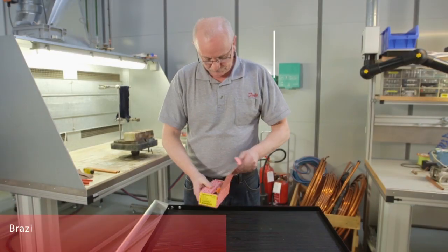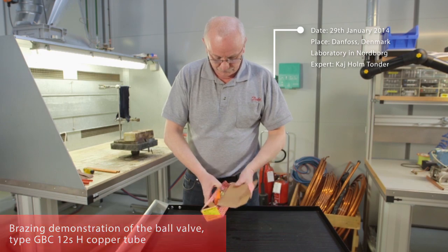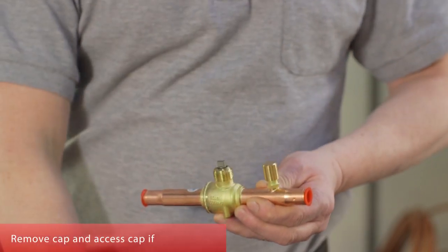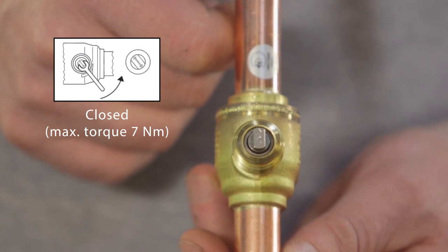Our expert will demonstrate how to braze the GBC 12s H copper tube ball valve. Read the instructions carefully. Remove the cap and the access cap if there is one. Here you can see the open and closed positions.